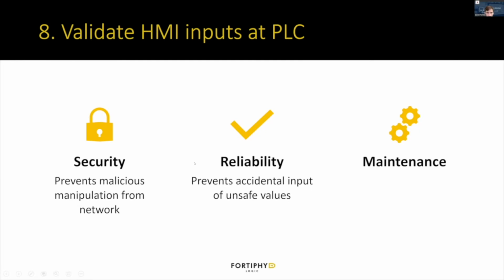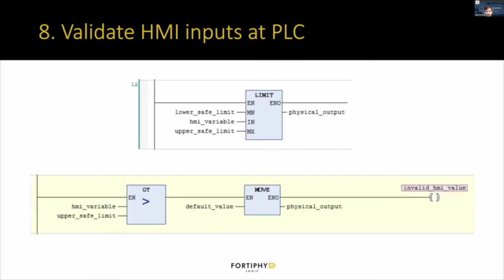For the example in CODESYS, we just use a simple limit function block, which clamps the value to a specified max and min safe range. We have some HMI variable coming in, we have lower and upper safe limits, and then the physical output is limited to those safe max and min values. You can also add checks to see if the HMI variable is above the upper safe limit. That means somebody from the HMI or just from the network tried to write a value that was too big, so we want to use the default value or a safe value and raise an alarm saying that we received an invalid HMI value.